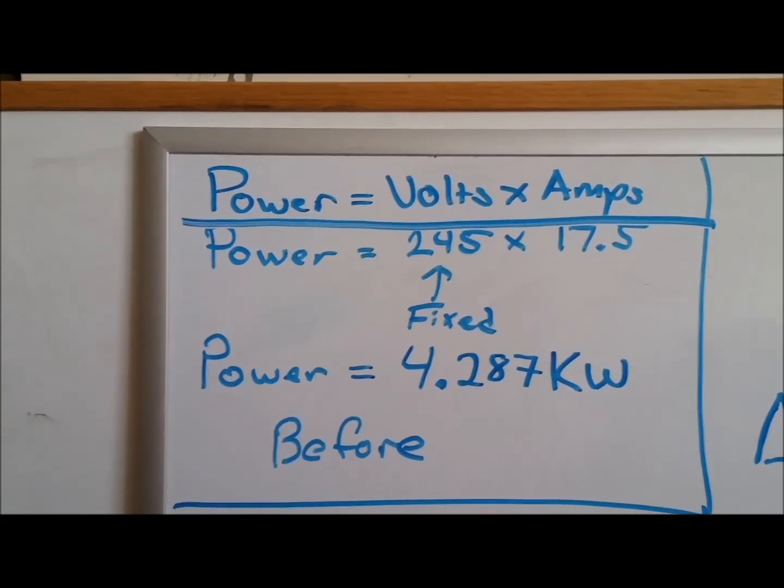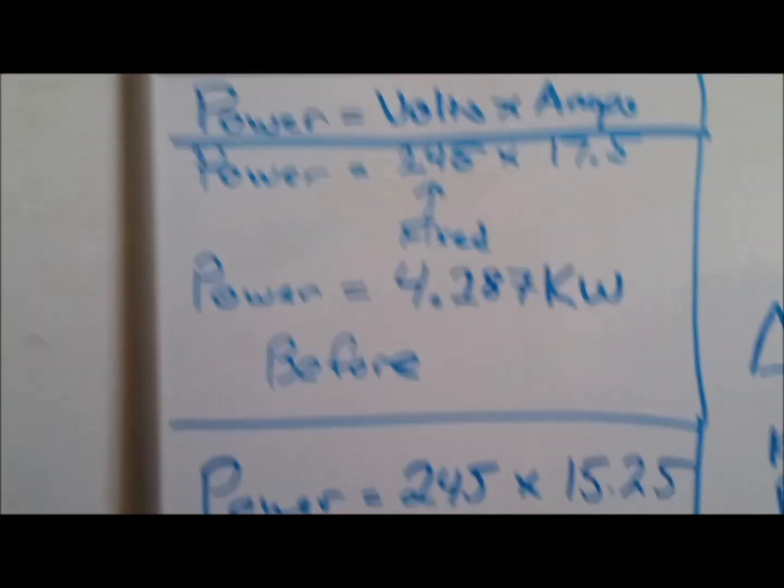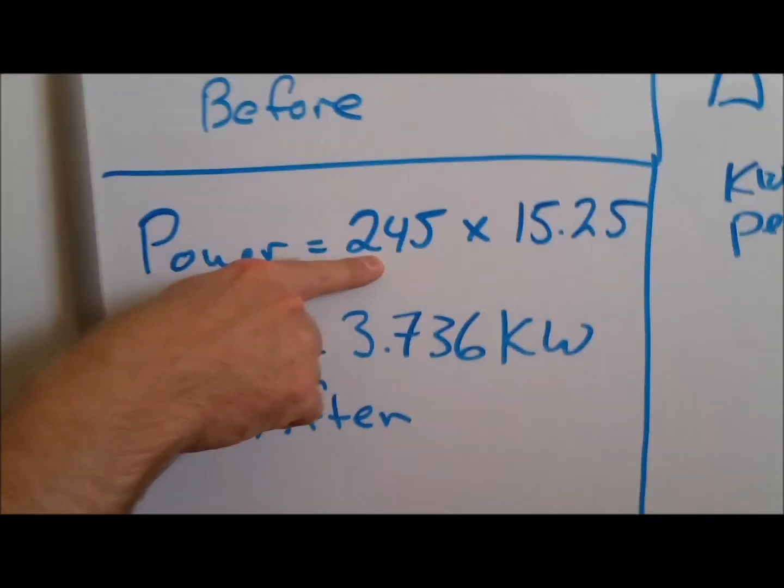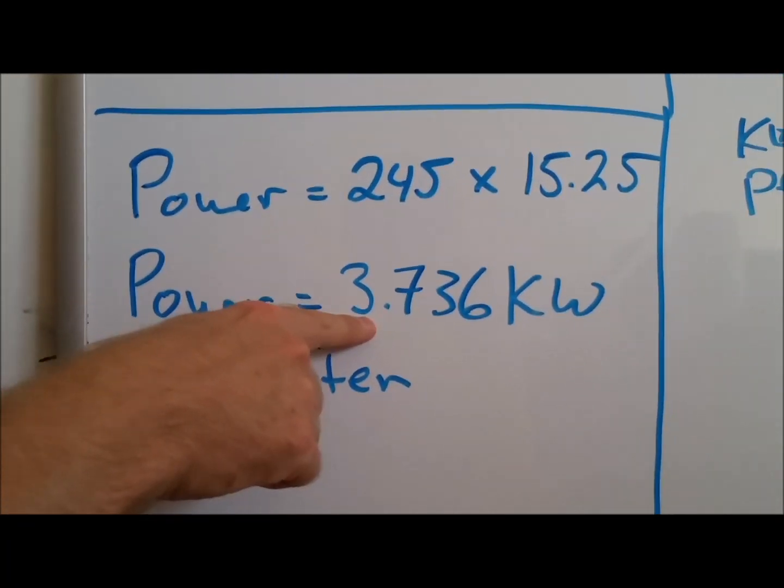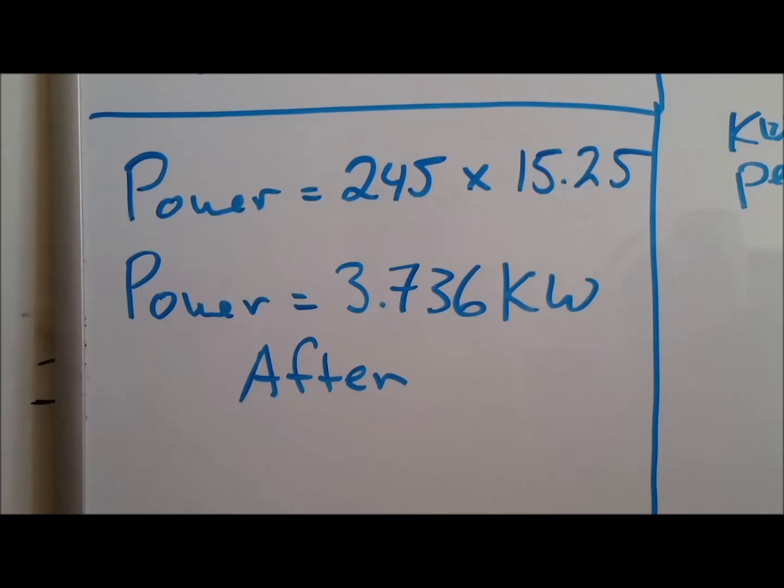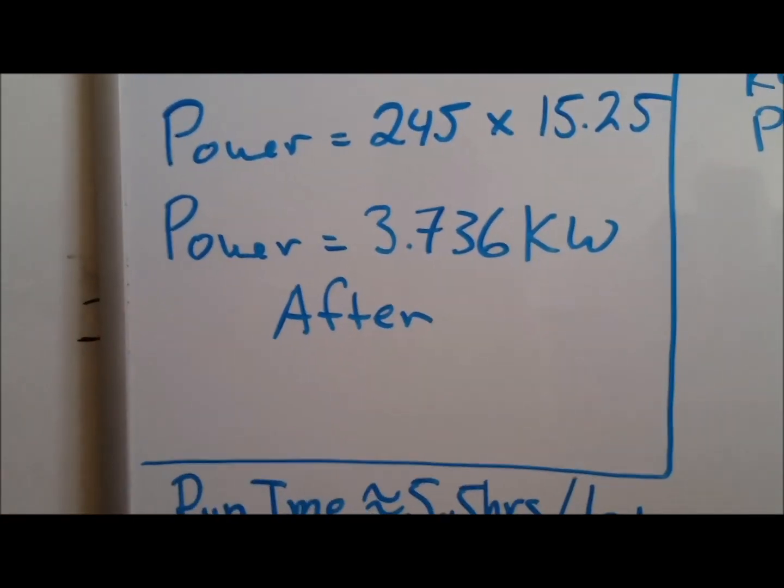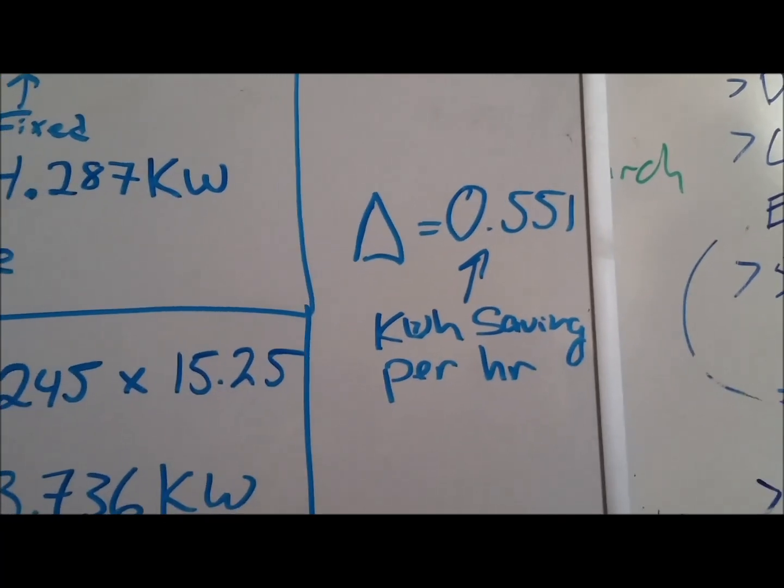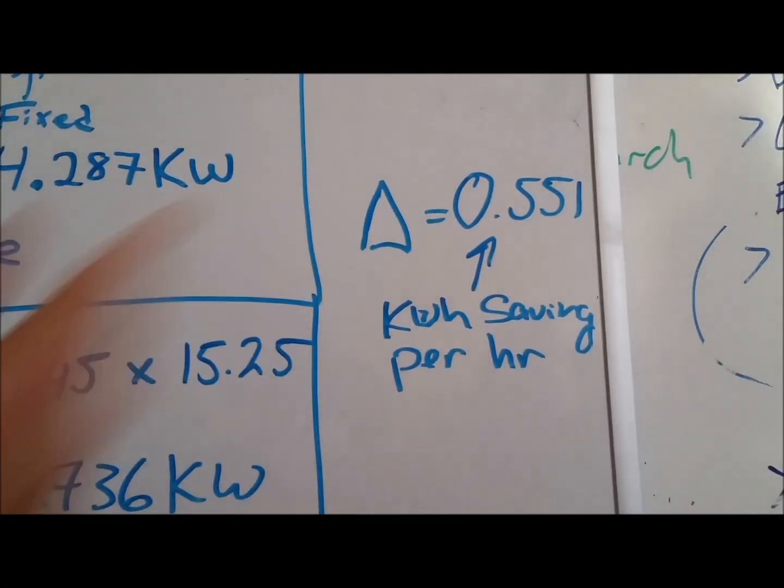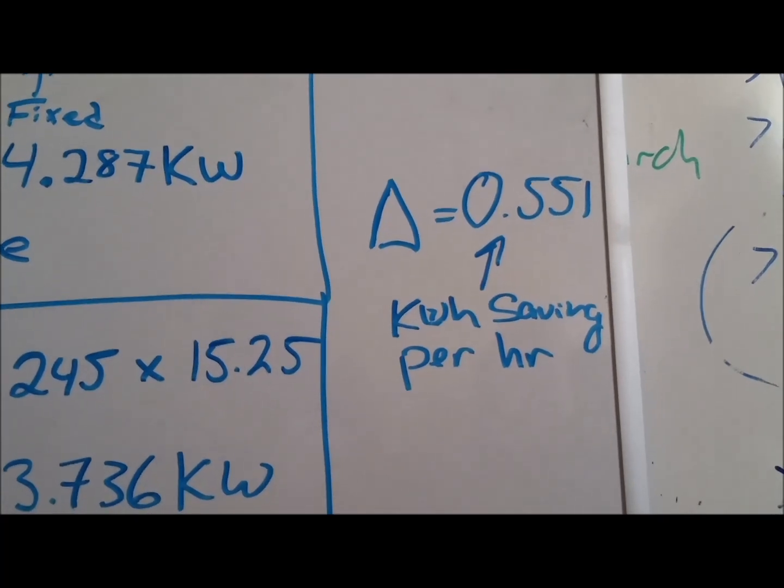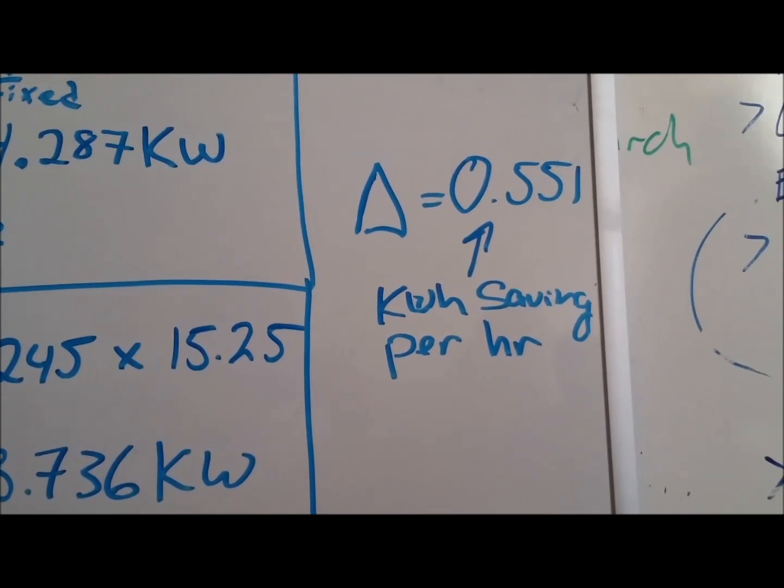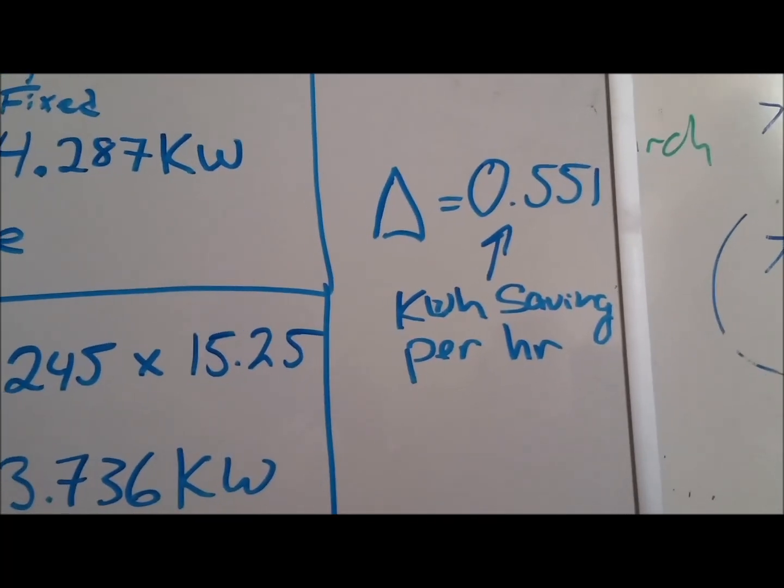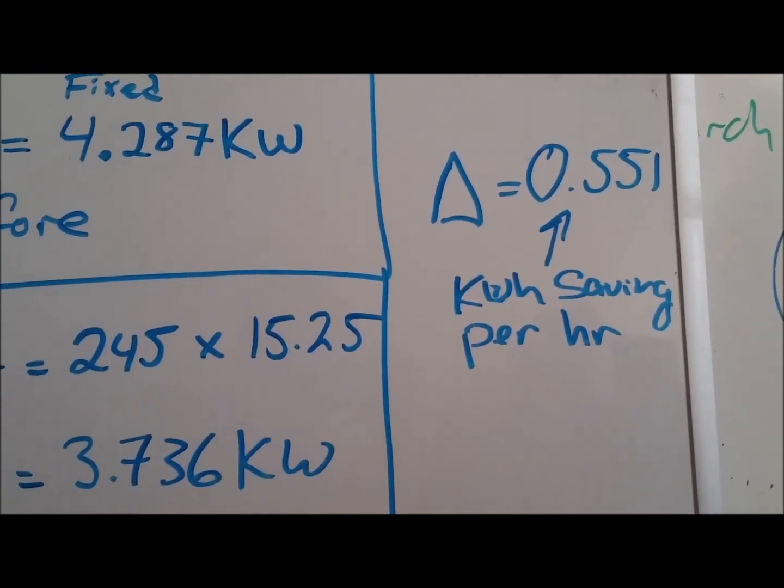Now if you run the same calculation again, 245 volts, 15.25 amps, your power calculation will now be roughly 3.7 kilowatts. And that's after the misters. So the difference between 4.287 and 3.736 is roughly 0.551 kilowatt hours per hour. So you essentially drop the power consumption by roughly 500 watts.